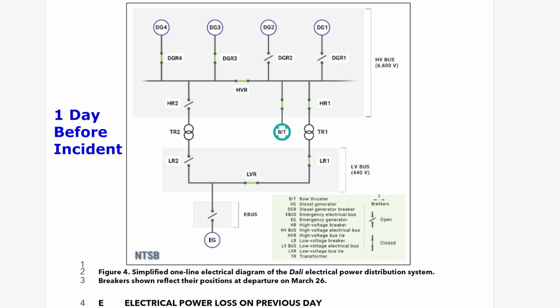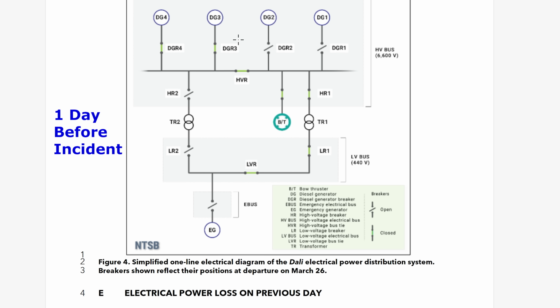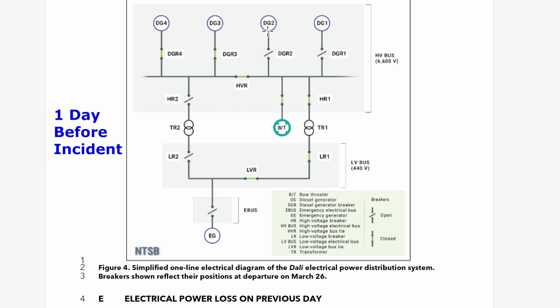So you might have heard that the Dali had lost power while sitting at the dock the previous day. And some people thought, well, maybe that's related. It really wasn't, but this is what happened there. So here's your diesel generator number 2. This is what was operating at the time. So during maintenance at the port, one of the crew members had accidentally closed the exhaust damper on the scrubber here. So that means that now it can't exhaust out to the outside. So that caused this generator here to stall.